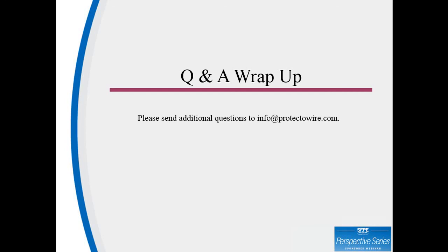Is the CTI Series and CTM module a standalone system? No, the CTM 530 interface module and the CTI Series linear heat detector are not a standalone system. Our UL listing and FM approval require two things. One, that the CTM module be connected to a listed or approved fire alarm control panel via relay contacts. And two, our listings and approval require that the CTM module and CTI Series linear heat detector be used together.